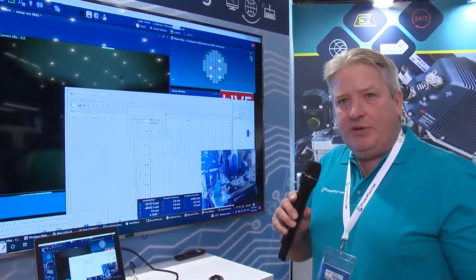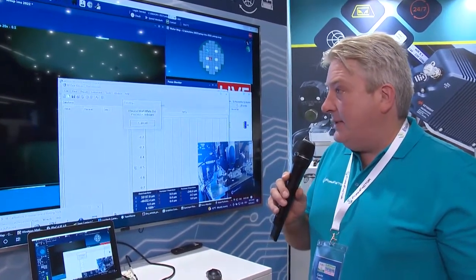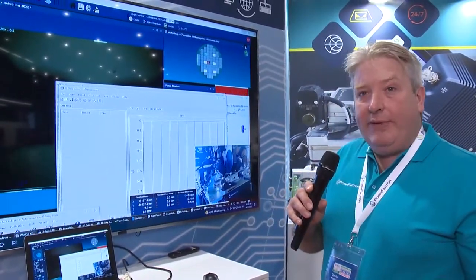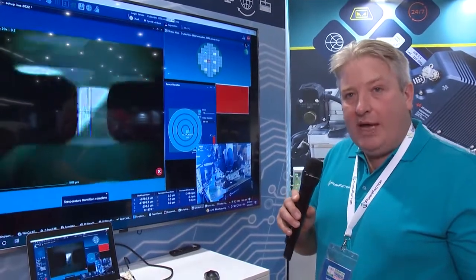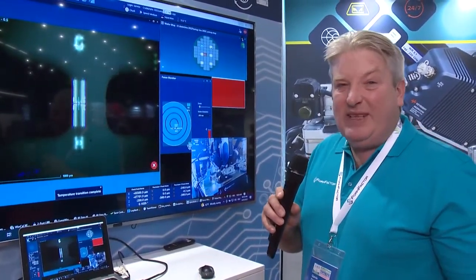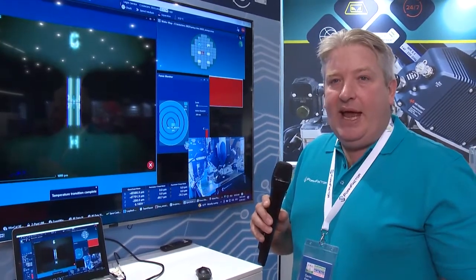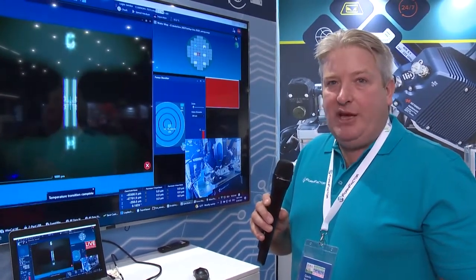So if you want to test them yourself, you literally just move there, just click that location, and you'll get the same effect. And then it will progress for the whole wafer. It will do a die step. If required, it will do a monitor to check that its data is going to be valid. If the monitor's failed, it recalibrates. If it hasn't failed and it's valid, it just goes and continues to measurement. And that enables you to do simple, accurate measurements, unattended and remote.